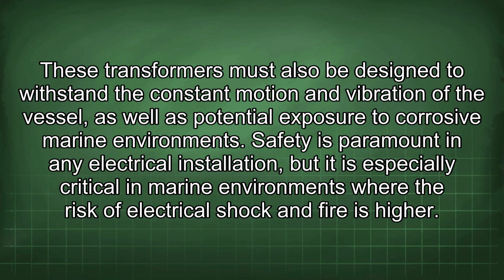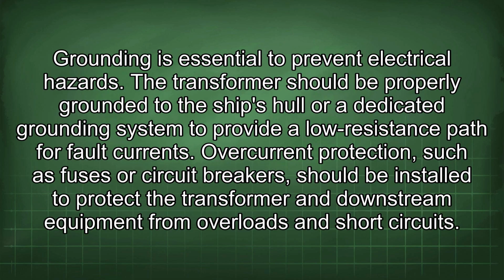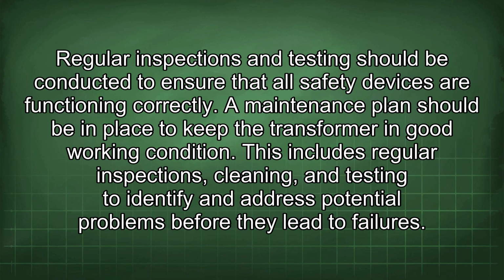Safety is paramount in any electrical installation, but it is especially critical in marine environments where the risk of electrical shock and fire is higher. Grounding is essential to prevent electrical hazards. The transformer should be properly grounded to the ship's hull or a dedicated grounding system to provide a low-resistance path for fault current. Overcurrent protection, such as fuses or circuit breakers, should be installed to protect the transformer and downstream equipment from overloads and short circuits. Regular inspections and testing should be conducted to ensure that all safety devices are functioning correctly.